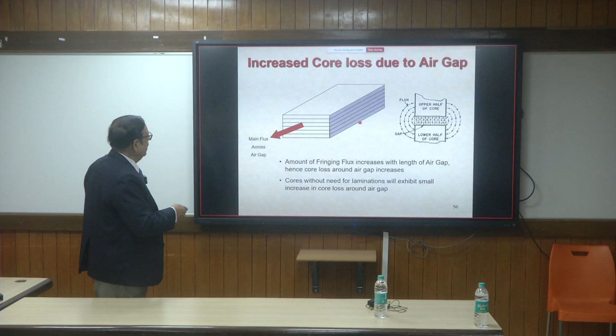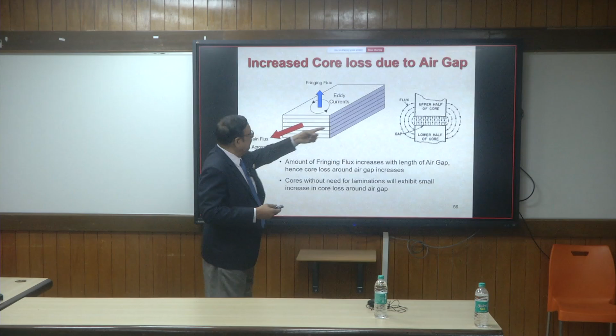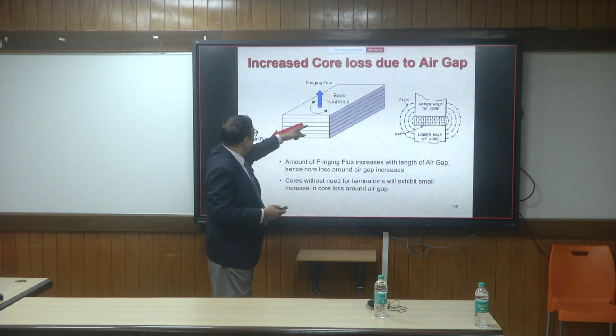Okay, when you have laminated inductors, as I had shown earlier, this is the direction of flux. But take a look at this figure now. Suppose this is an air gap here. Much of the fringing flux is coming out at 90 degrees to the surface, which means the flux is coming out in this direction, and you do not have any lamination in that direction, so it will form an eddy current. If that happens, you have high losses in this local area, and the temperature near the air gap around this point can become very large for the core, and it can lead to damage of the insulation of the winding. And that heat is not generated by the coil. It is generated because the fringing flux is coming out at 90 degrees, and you don't have lamination for that. You have lamination for the main flux.